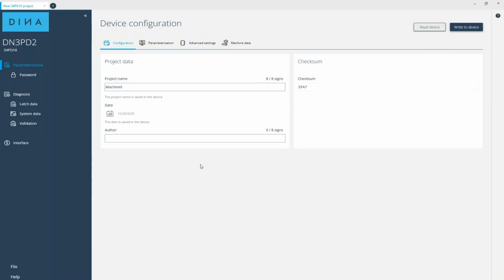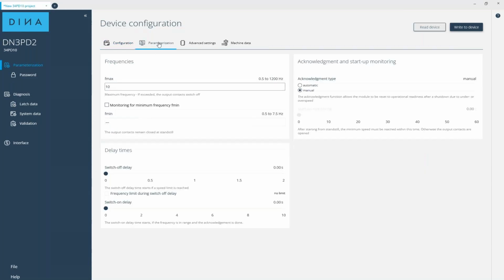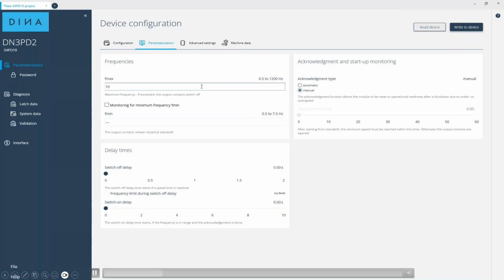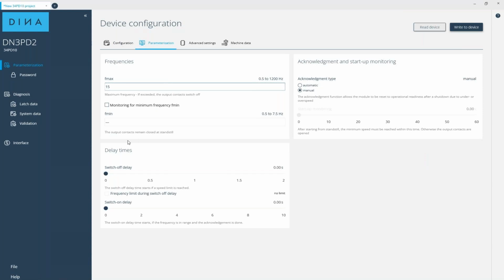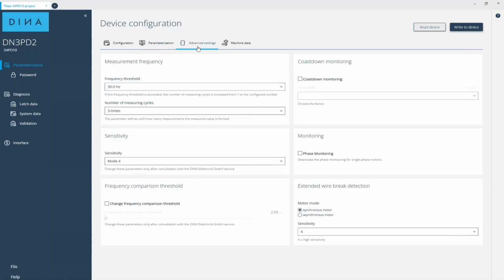In our case, we select as example the 34PD10, and we jump automatically or move to the configuration page where we can set the project data, for example, the name and author of the project, which is important for later documentation. And the tab parameterization, here we can set the main safety rules. This means setting the maximum and minimum frequency or speed limits. You also set delay times and how the module should be reset after stop.